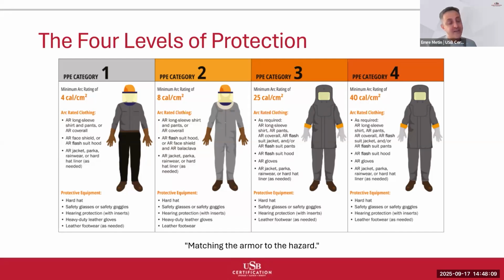Category 4, arc-rated long sleeve shirt, arc-rated pants, arc-rated coverall, arc flash suit jacket and/or arc flash suit pants, arc flash suit hood, arc-rated gloves, arc-rated jacket, parka, rainwear, or hard hat liner as needed. Notice how the protection becomes more comprehensive at higher categories. This isn't arbitrary. It reflects the increasing severity of potential thermal injury at higher incident energy levels. The key principle: you are matching the armor to the hazard. The protection level must be appropriate for the specific energy level workers might be exposed to.